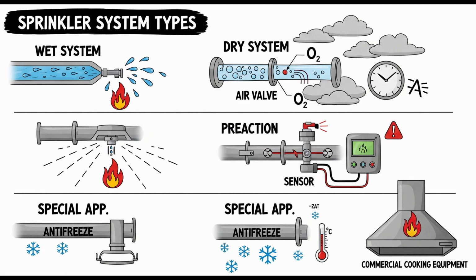It's definitely robust. For systems with more than 600 sprinklers total, or more than 275 sprinklers in any single fire area, the entire system must be controlled by two 6-inch dry pipe valves installed in parallel, feeding into a common main pipe. Two large 6-inch valves working together. That really emphasizes capacity and redundancy. It absolutely does. These parallel valves must be checked against each other, meaning they work in concert. Each dry pipe valve has its own listed tripping device that's actuated by the fire detection system.